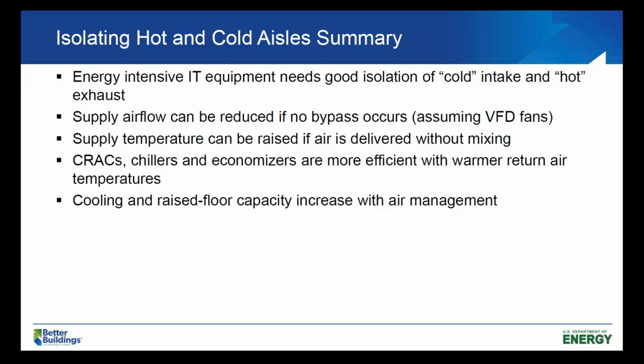The cooling system capacity and the ability of the raised floor system to deliver cooling are increased with air management. You can get closer to the rated performance of the cooling equipment with good air management. The other thing that's important to remember is the IT equipment will be happier because it's getting a more uniform air temperature delivered to it, and fewer pieces of equipment will be outside the recommended range. Next slide.